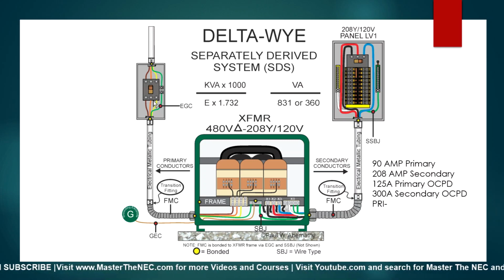These conductors that we're running down are rated 2 gauge, because they're good for 115 amps at 2 gauge, but we're terminating on a 125 amp breaker, so we want to make sure they're protected at their ampacity. So we wanted this to do double duty. We're at a 125, so that's going to protect the transformer as well as the conductors. And if you didn't understand any of that, you need to go back and watch episode 2 of this series to understand why we did that.